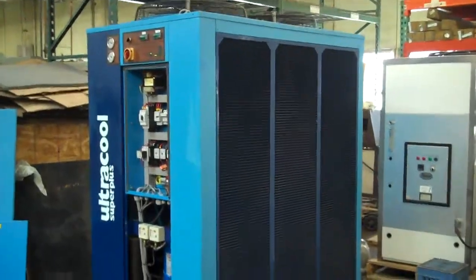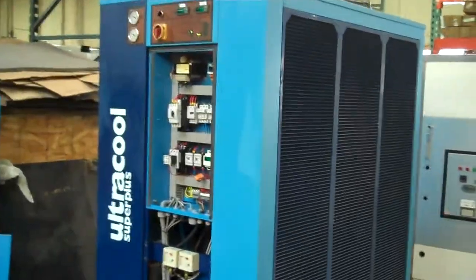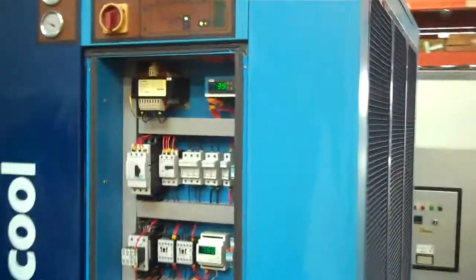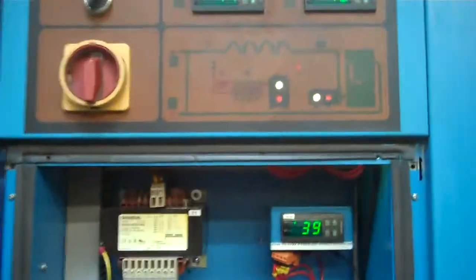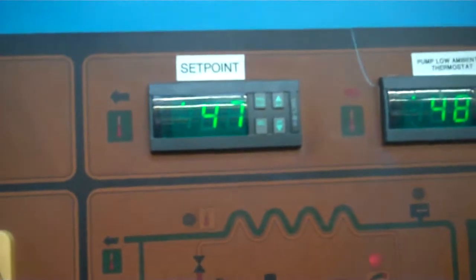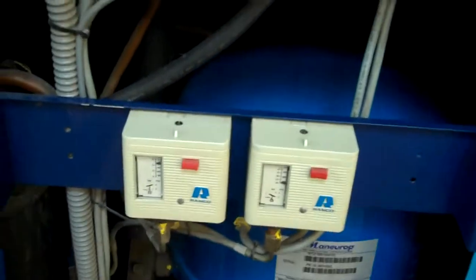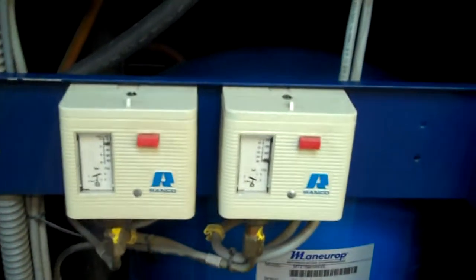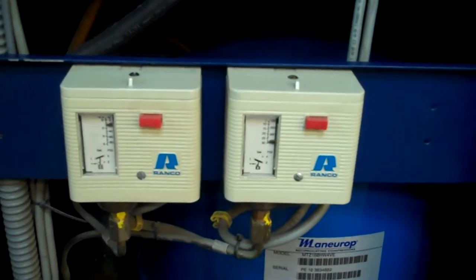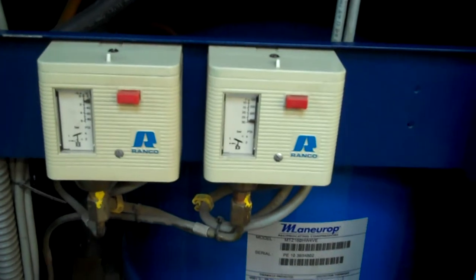This is our video number 3 for our Donaldson 13-ton chiller, as we're starting to get close to the set point of 42. We're down to about 47 right now. By the way, those are the low and high refrigerant pressure switches. Shouldn't have to change those at all either. Those are preset at the factory.